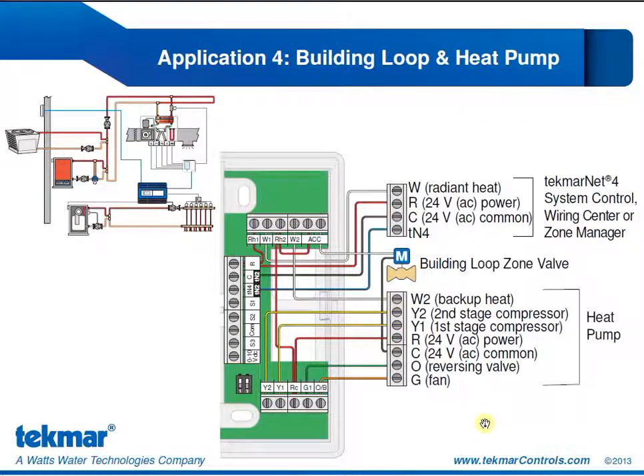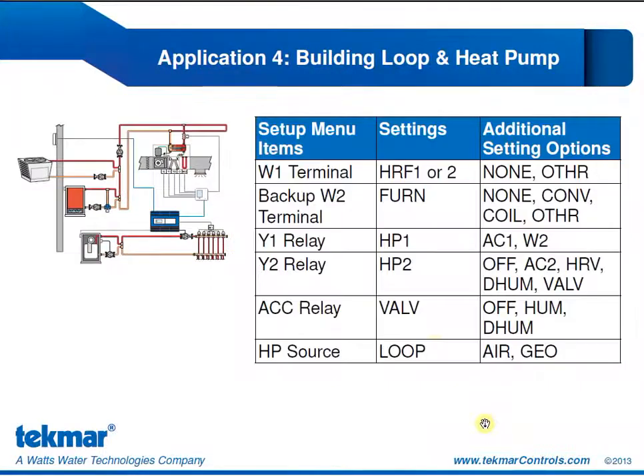For that backup electric strip, we have, again, R coming in from the heat pump up to RH2, which is connected to W2, W2 back to the heat pump for the operation of the electric strip backup.